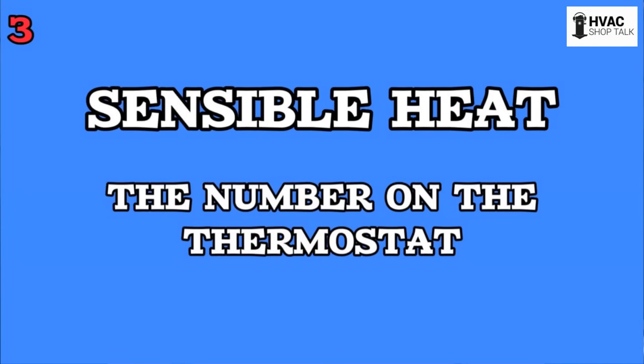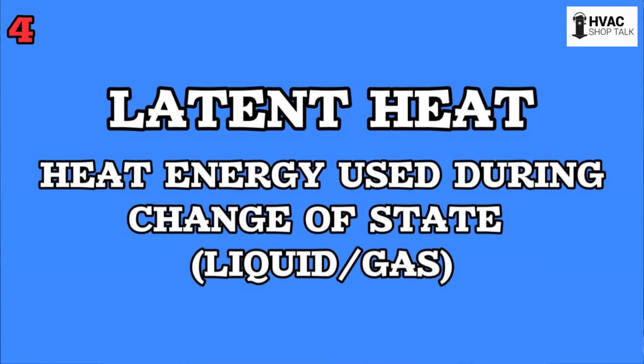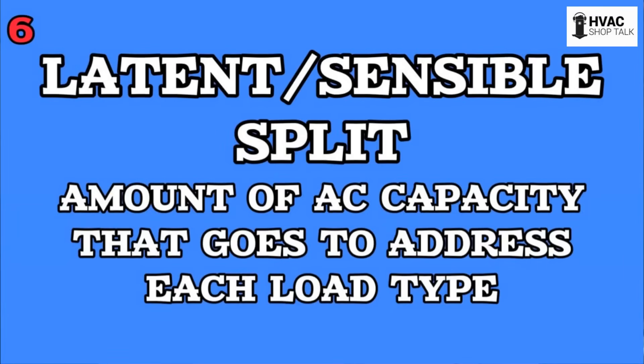The more humid your air is, the more capacity it needs in the latent category. So think about it: sensible is the number on the thermostat, and latent — you can think of it as the relative humidity number if your thermostat has that. You combine those two to get total heat. In certain environments with less humidity, you don't require as much latent capacity, and the latent/sensible split swings based on how much capacity you need between latent and sensible load types.